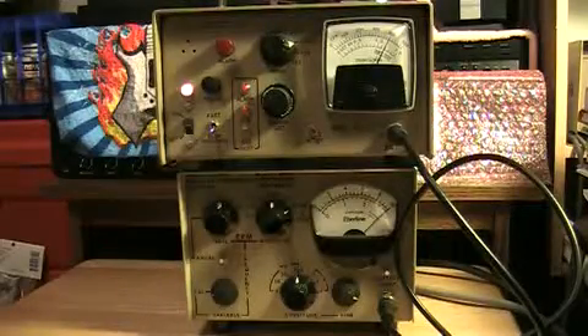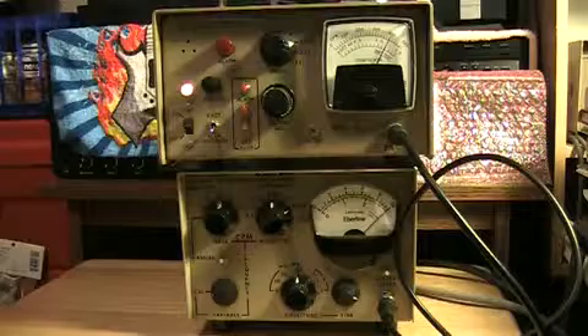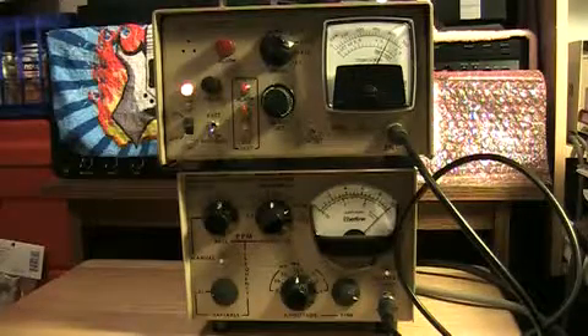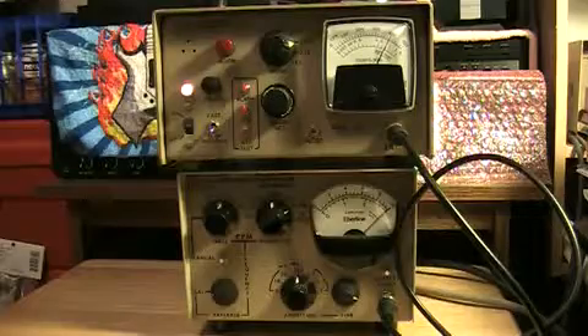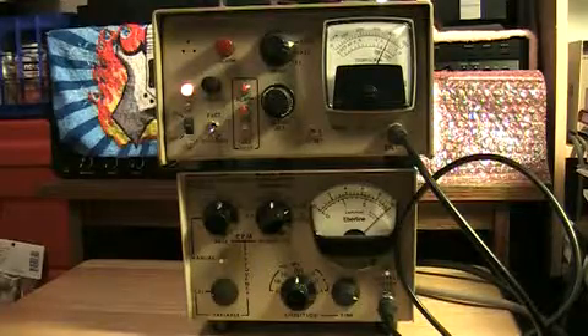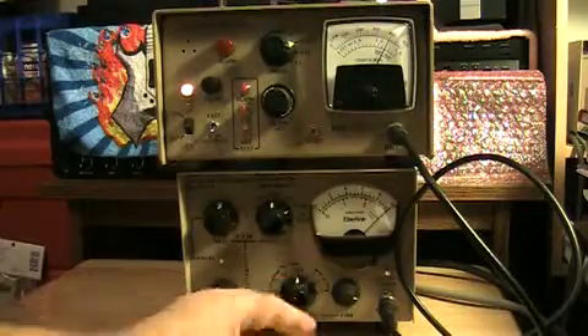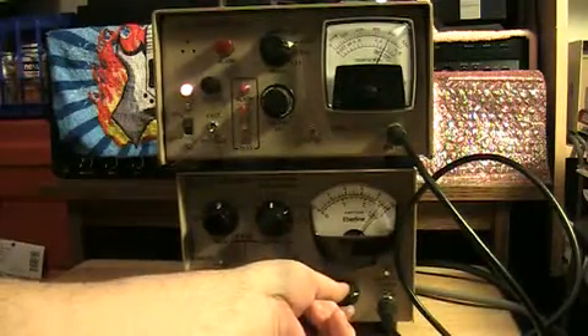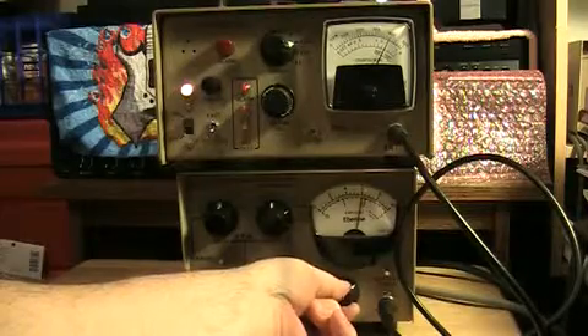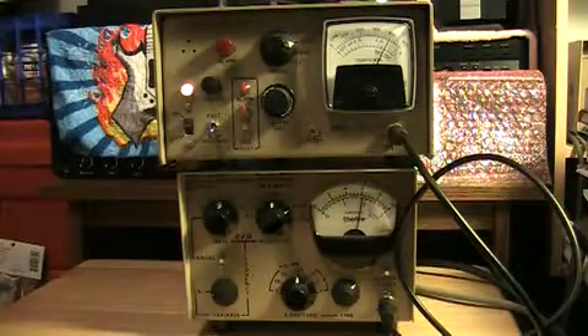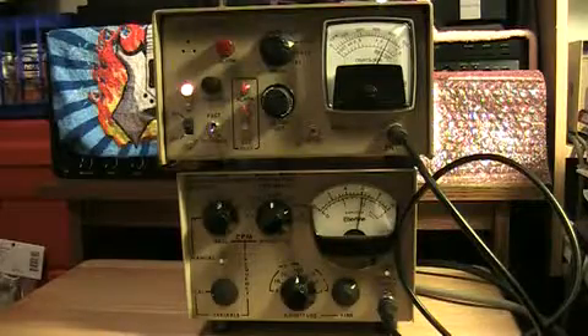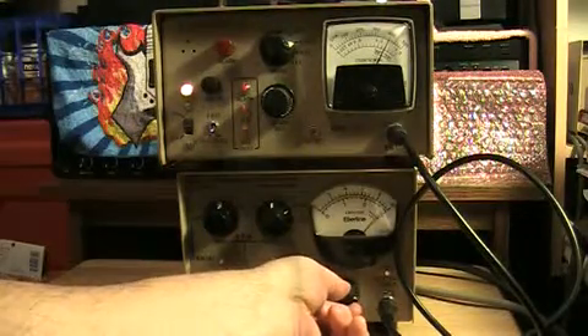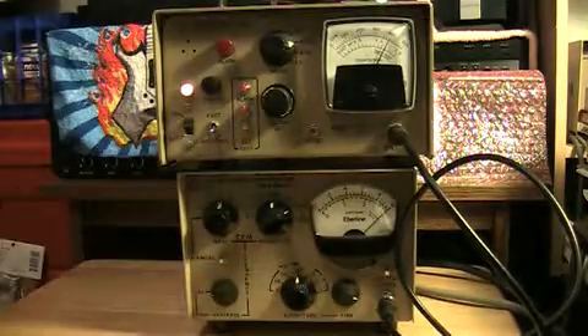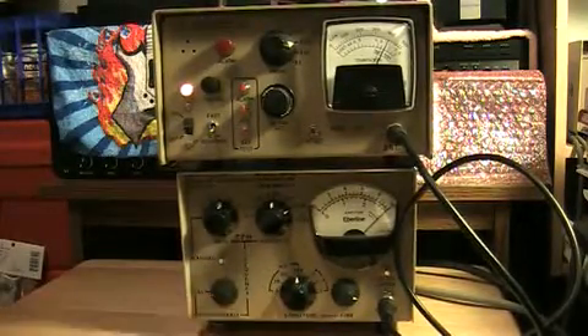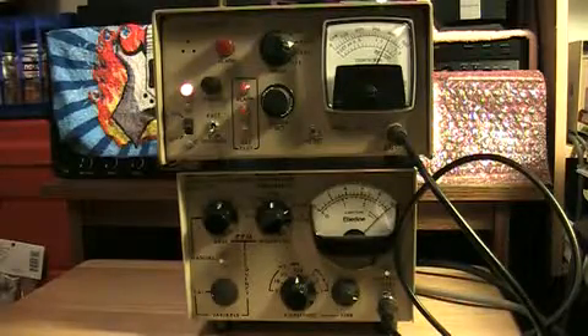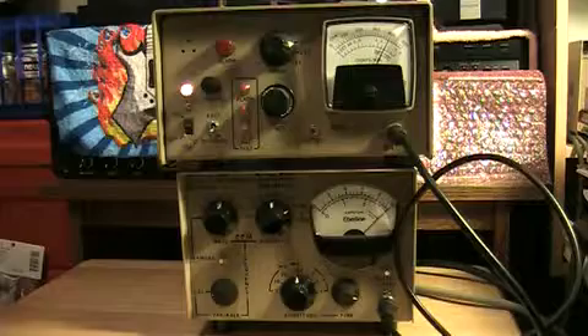So there you have it. And that's a very simple routine on how I calibrate. I didn't show you the actual turning of the pots in the back, but most of these are set for 100 millivolts. This is fine tuning here. You can adjust it to say there's maybe 60 millivolts, 80, and then 100 millivolts. Goes up to 3 volts, down to 0.3 millivolts. You can go to manual if you want to manually adjust the counts.